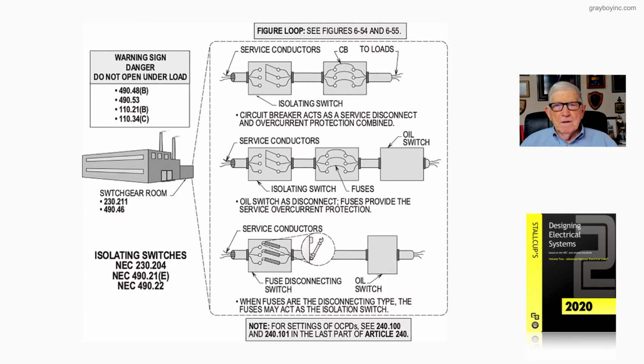Now you notice the isolation switch in the top illustration has service entrance conductors coming in with a disconnect, and a circuit breaker is used to disconnect, say, an oil switch type switch, or just serve as a protection to the equipment. So you have a circuit breaker there with disconnecting means to isolate that circuit breaker, if you need to repair it, work on it, or service it in some way in accordance with Annex K and Chapter 7 of 70E, as well as Chapter 17. When I say 70E, I quoted that wrong, 70B.